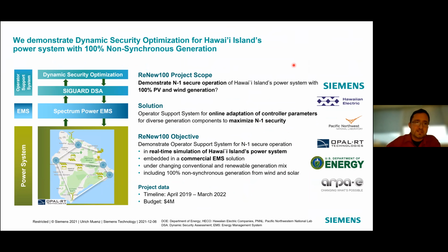What we developed for this is a system we call an operator support system. Think of it as an assistance system like in your car, which dynamically adjusts the parameters of your system to make sure you're always N-1 secure. As I said, the eigenmodes of your system change not within minutes but within hours, days, or weeks, so you continuously adapt the system to keep it N-1 secure. That way we can also scale it to large systems where eigenmodes change and may not repeat for a long time.